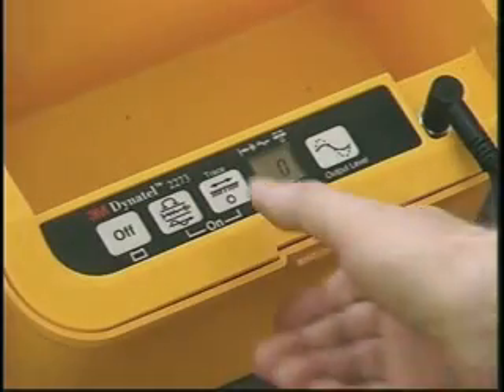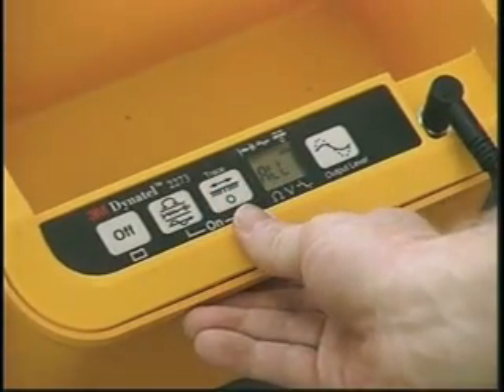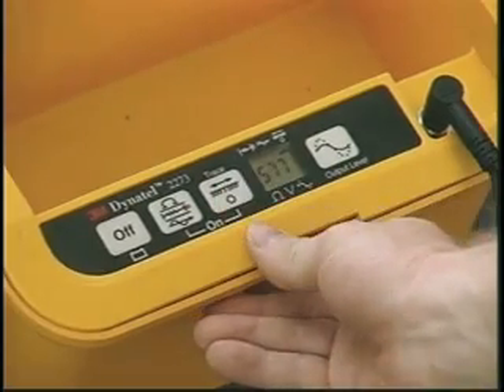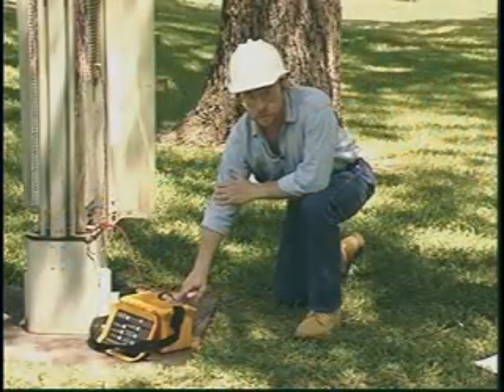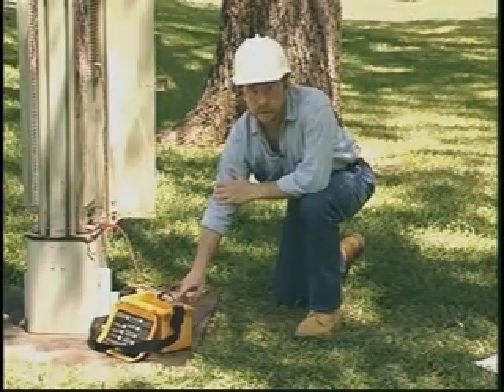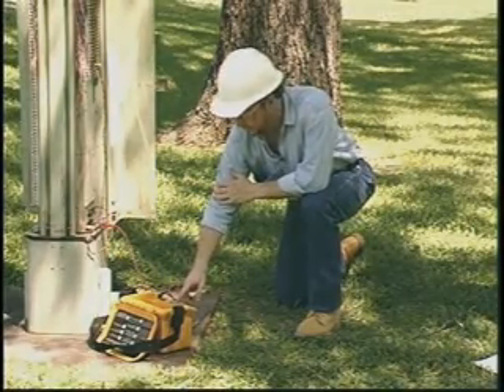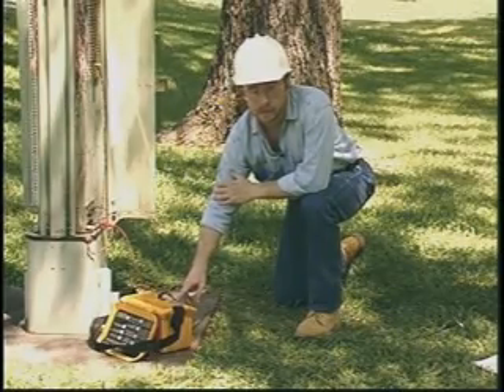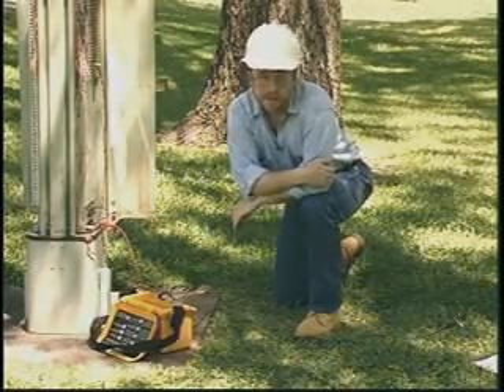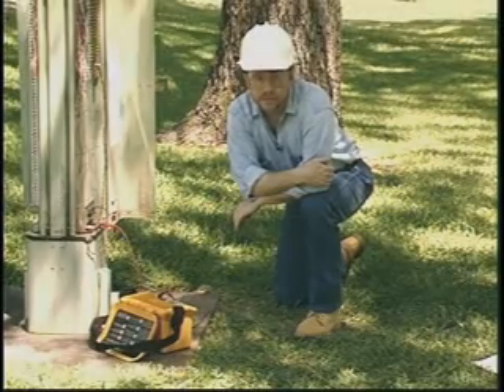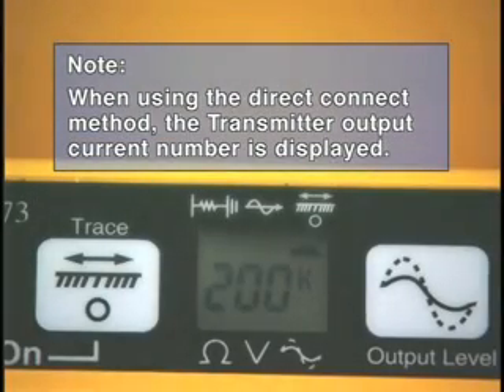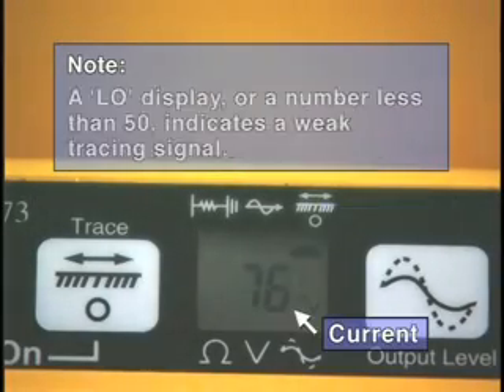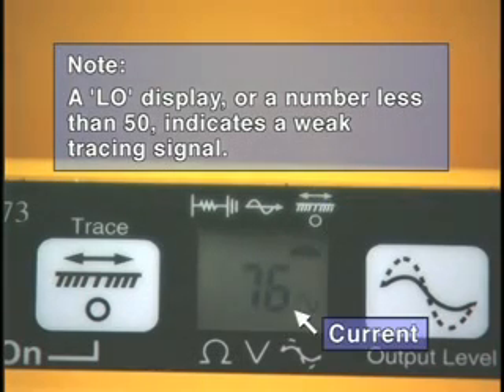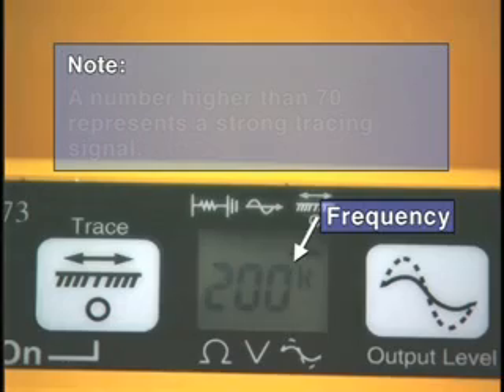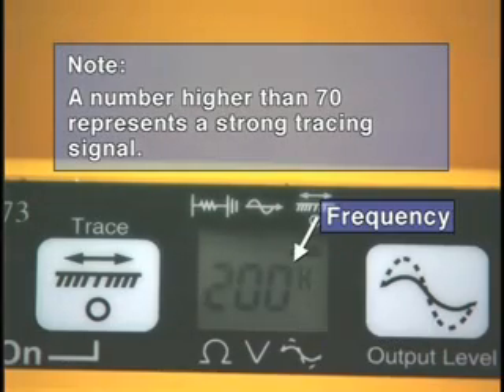If the circuit is good, press the trace key and select the 577 Hz frequency. You should use this frequency with the direct connect method when the far end is bonded. If it's not bonded, use 33 kHz or 200 kHz. For longer tracing distances or deep cables, you can apply a higher output by pressing the output level key. When using the direct connect method, the transmitter output current number is displayed. A display of the word low, or a number less than 50, indicates a weak tracing signal. A number higher than 70 represents a strong tracing signal.